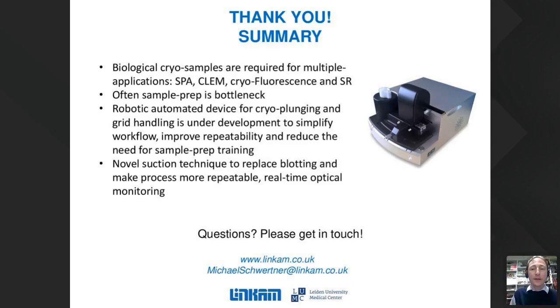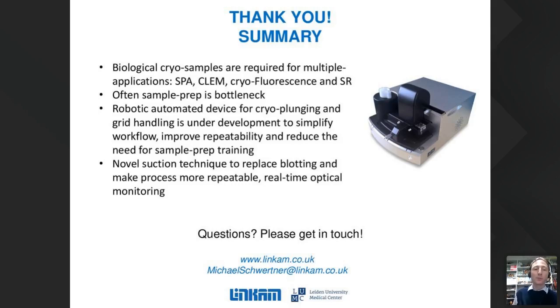To summarize: cryo samples are required for many workflows — most importantly single particle analysis to determine protein structures, CLEM correlative light and electron microscopy, and cryo fluorescence. Sample preparation is quite often the bottleneck and we tackle this with the automated plunger system, which uses a completely different technique for blotting and removes much of the skill required from the operator because handling is all done in an automated way.